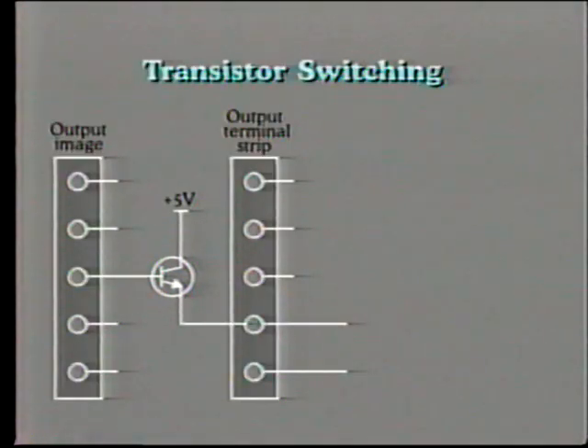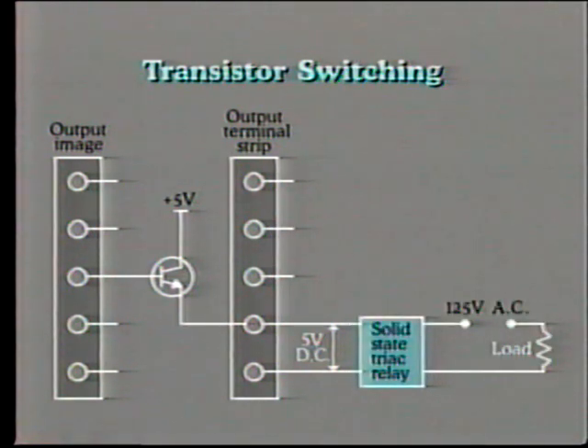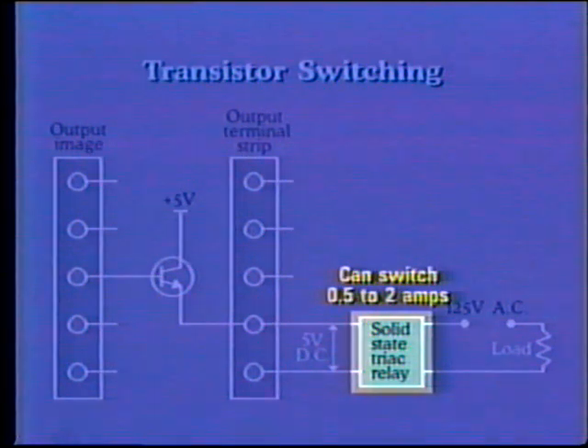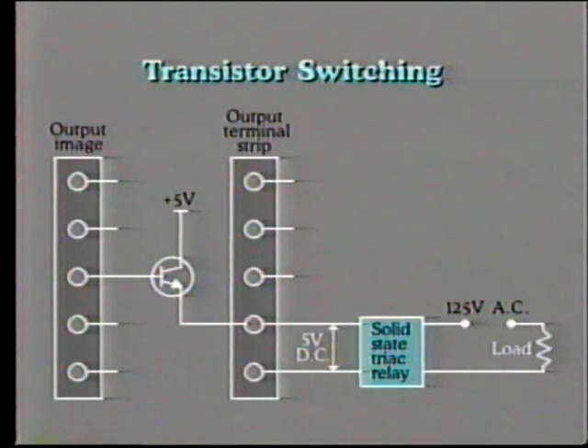Where AC switching is required, the DC output signal from the PLC is used to trigger an external or internal solid-state relay, such as an optically isolated triac. These devices usually have the capacity to switch 0.5 to 2 amps.